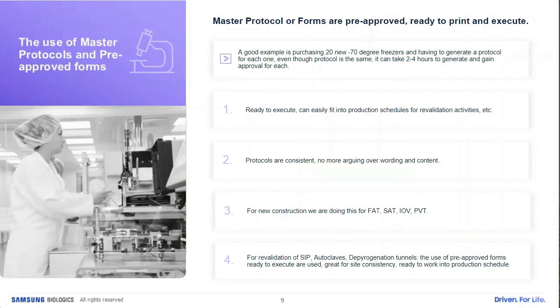So for this -70 freezer, we can create a master protocol which is pre-approved. It's been through all the signatures, signed off. What we want to do is take that master protocol, print it out and execute. That same master protocol is used for all 20 of those -70 freezers. So you could validate all 20 at the same time without having to route a separate protocol for each one. So using a master protocol, they're consistent. There's no more arguing over wording and content.